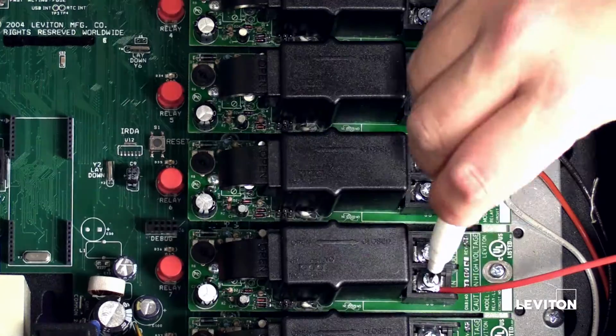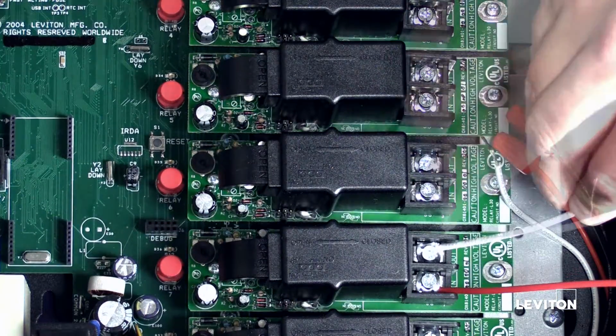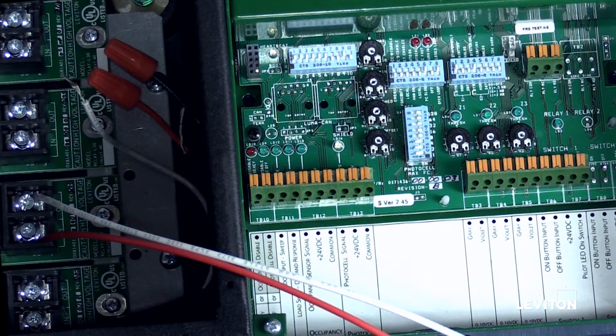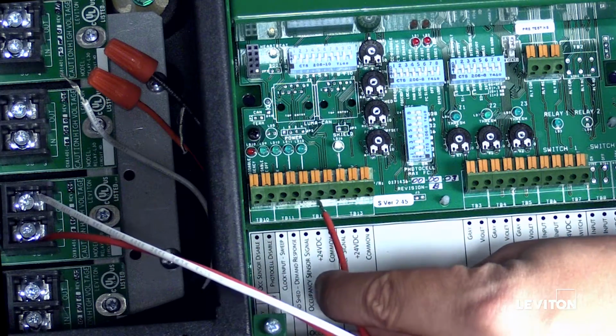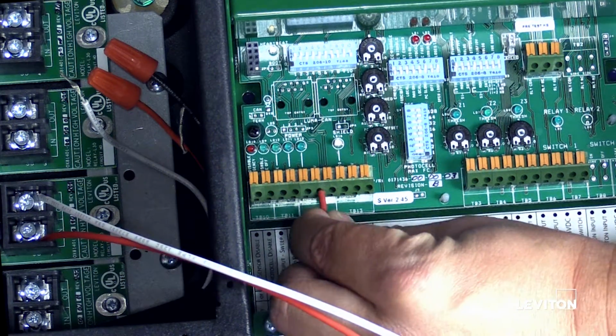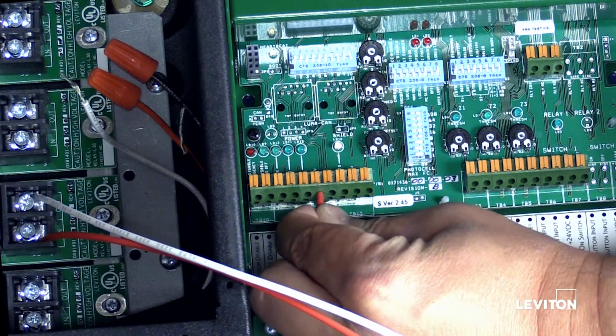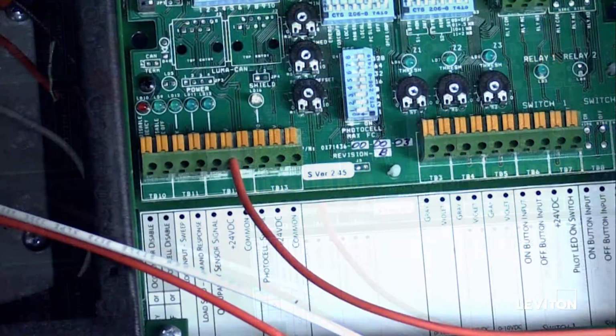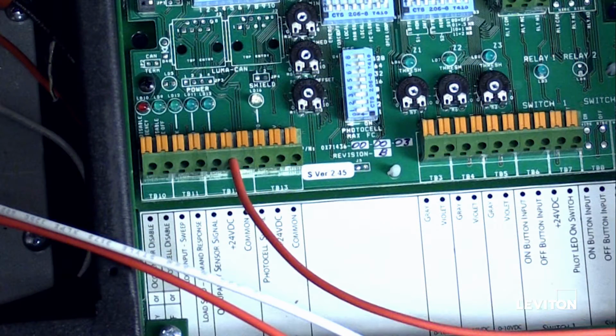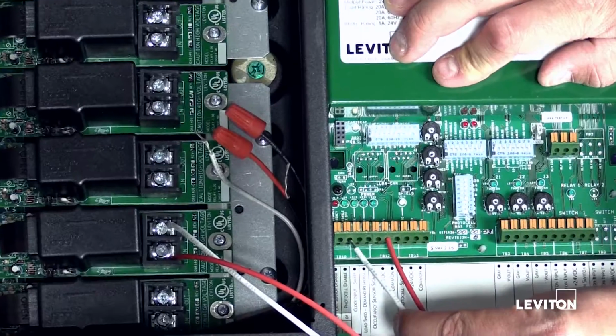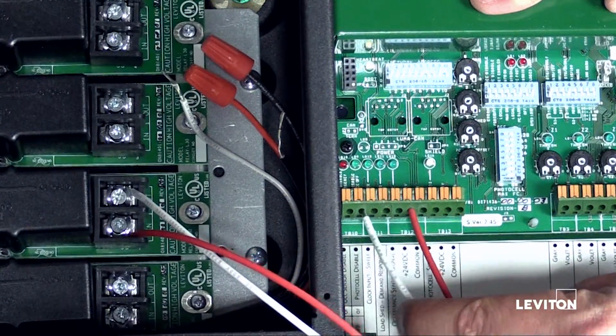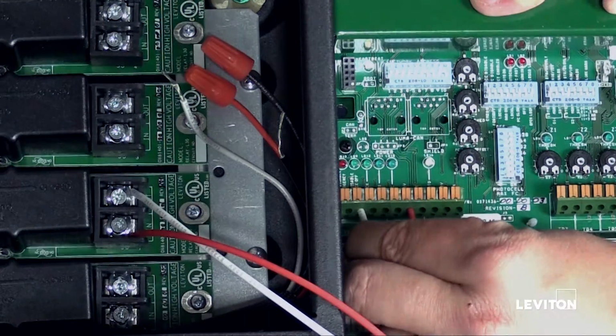Install 18 gauge wire on each side of the relay. Land the plus 24 volt DC wire onto a connector labeled plus 24 volt DC. Note, you can land the plus 24 volt DC wire onto any connector labeled plus 24 volt DC. Land the return wire onto the connector labeled force off.